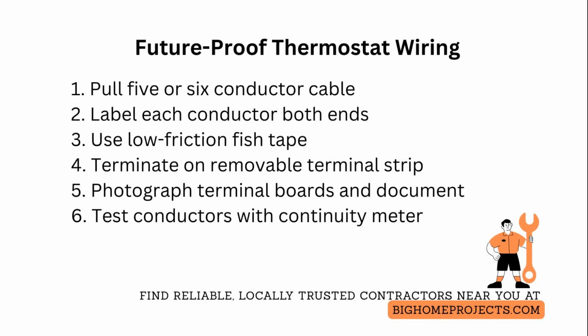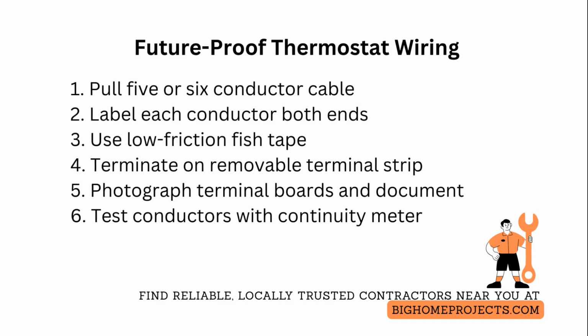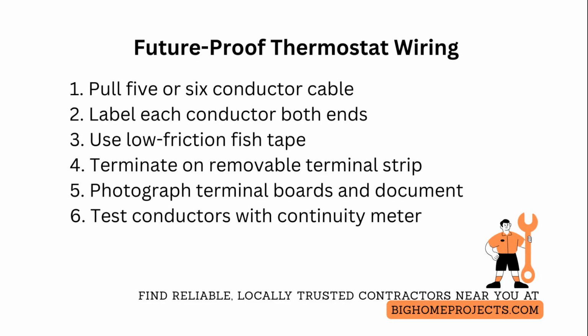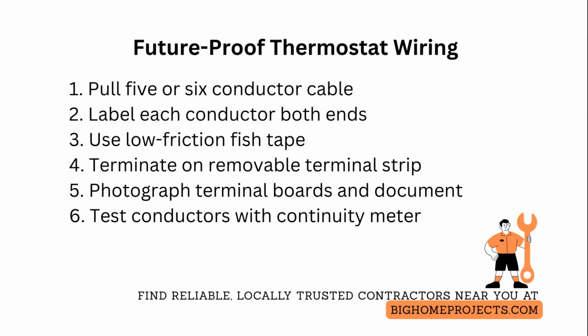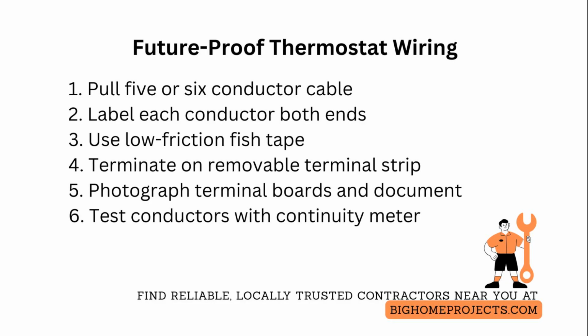When fishing through walls, use a low-friction fish tape, a small diameter pilot drill or inflatable conduit to protect sheathing and avoid insulation compression. Keep cable runs straight and avoid tight staples that nick the jacket. Terminate wires on a removable terminal strip at the equipment end so you can swap or add devices: humidifier, zoning damper, outdoor temperature sensor, without soldering.